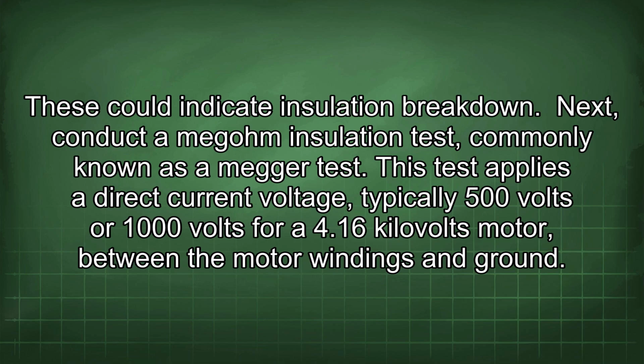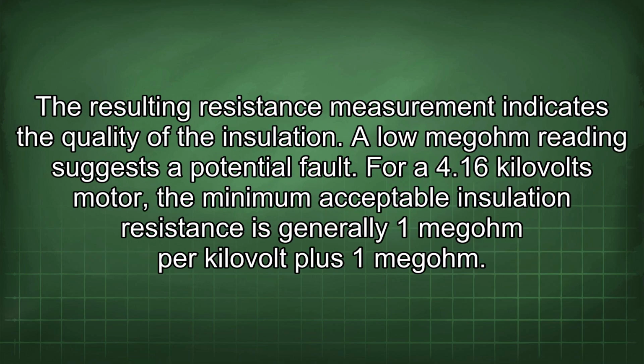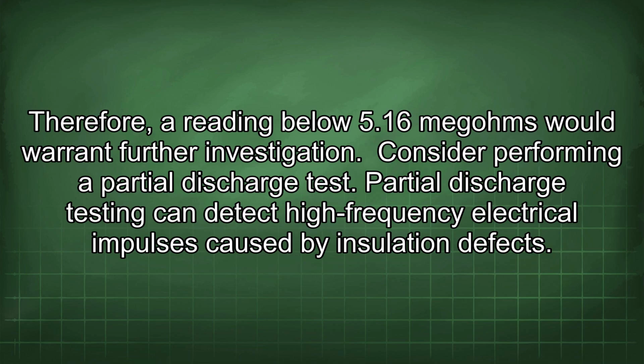Next, conduct a megohm insulation test, commonly known as a megger test. This test applies a direct current voltage, typically 500 volts or 1000 volts for a 4.16 kilovolts motor, between the motor windings and ground. The resulting resistance measurement indicates the quality of the insulation. A low megohm reading suggests a potential fault. For a 4.16 kilovolts motor, the minimum acceptable insulation resistance is generally 1 megohm per kilovolt plus 1 megohm. Therefore, a reading below 5.16 megohms would warrant further investigation.